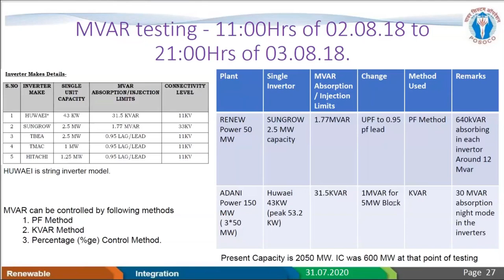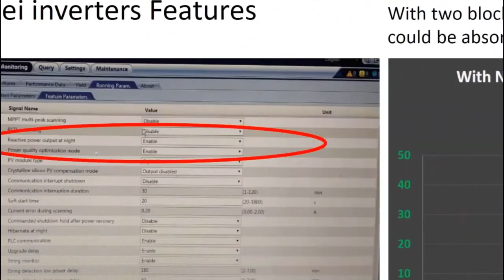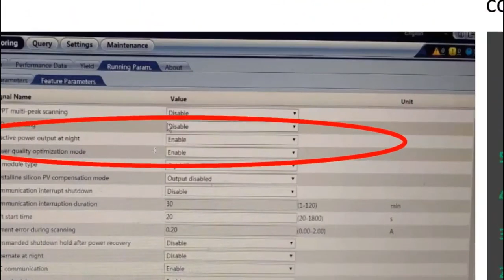Just to show you, the Huawei inverter. You see there is a question of whether they can support at night. I hope the screen is visible: reactive power output at night. There is one feature in the inverter which we enabled for testing purposes, and we tried to test a limited MVAR. You can see this is the night where we could get 30 MVAR from that operation. Of course, this is only a 50 megawatt plant, and the higher side is also limited, but we could get 30 MVAR without any generation, to establish that yes, in solar power parks, with inverters we can get the support.